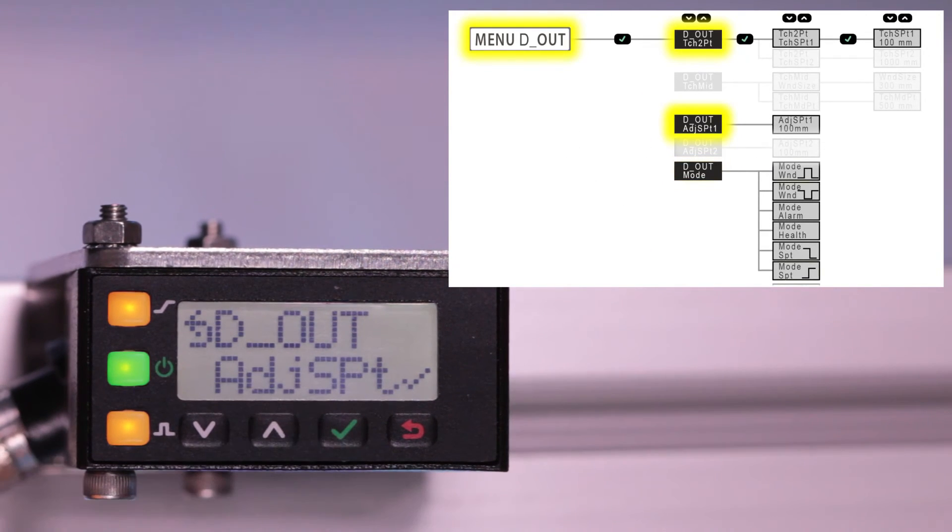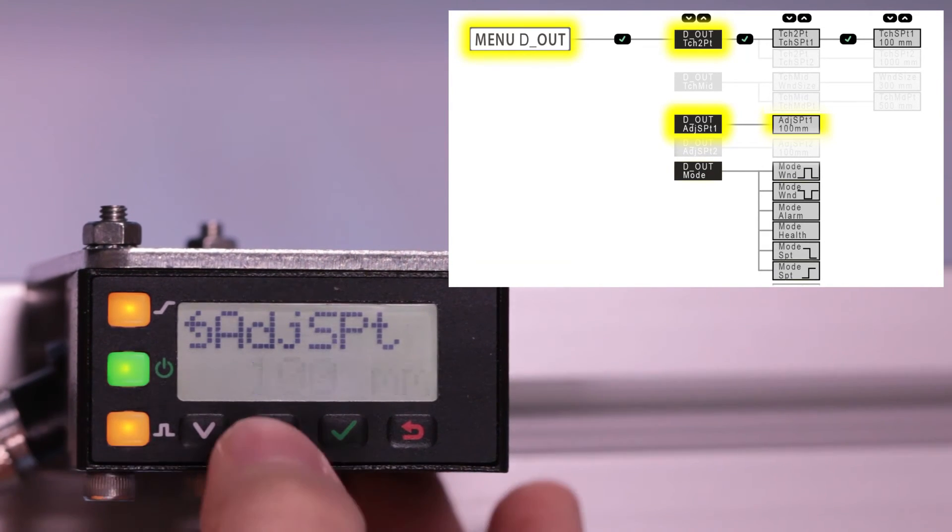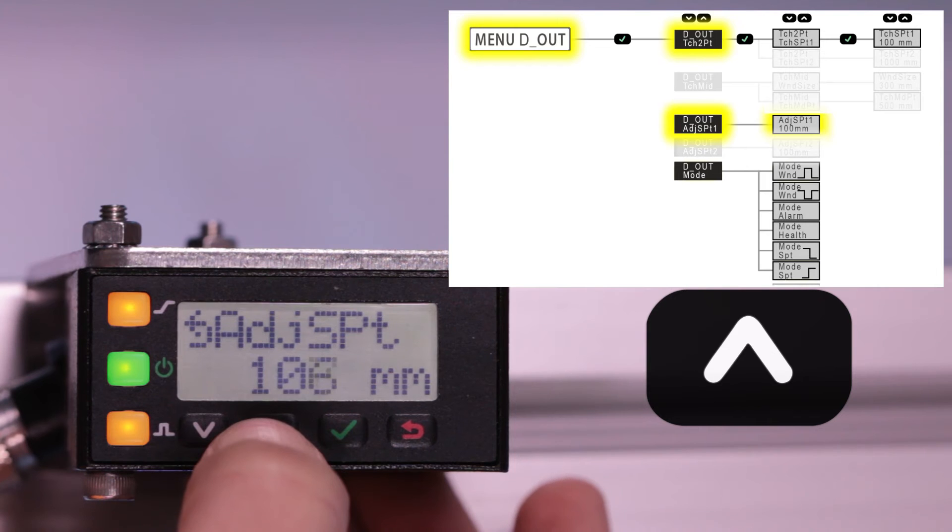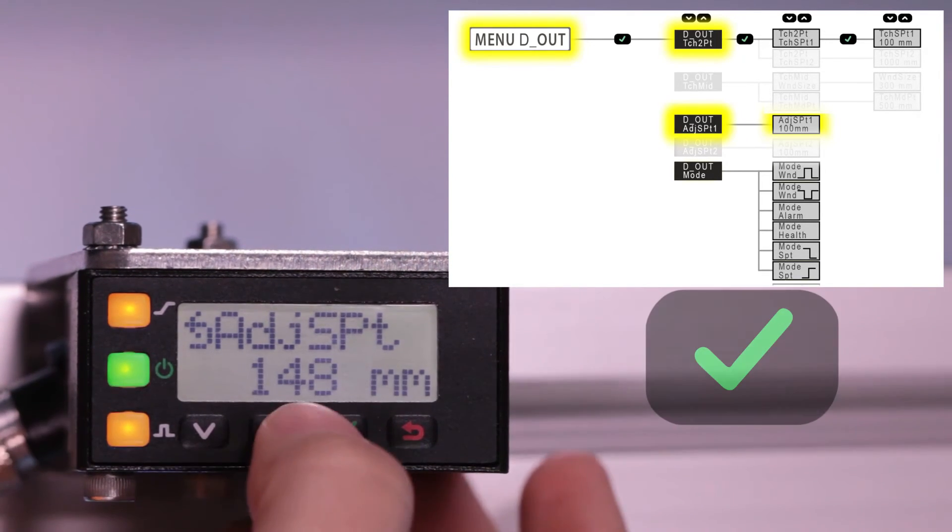Click up to go back to the adjust switch point menu option and click enter. The value will now start flashing, indicating that it can now be changed. Click up to move the switch point to 148mm.